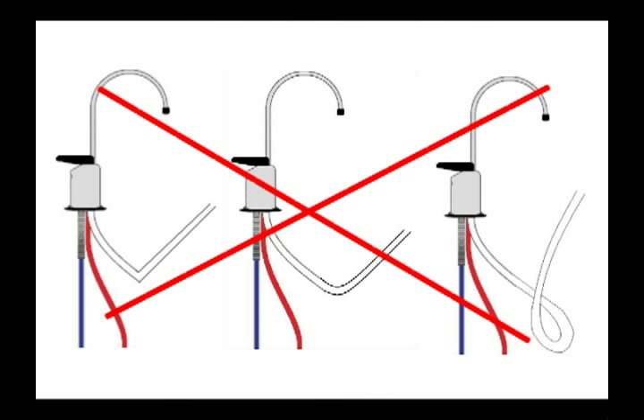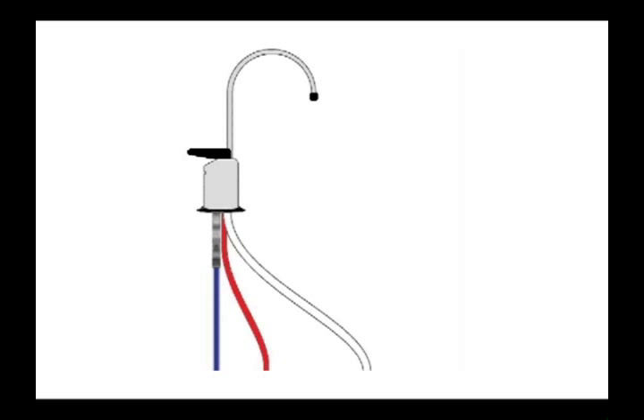Examine the tube running from the air gap into the drain. This is usually the largest diameter tube in the RO installation. This tube is a gravity driven line and must go straight down to the drain. There should be no kinks, dips, or loops found in this tube. If you notice any type of low spots or kinks, cut the tube so it reaches the drain as short and straight as possible.